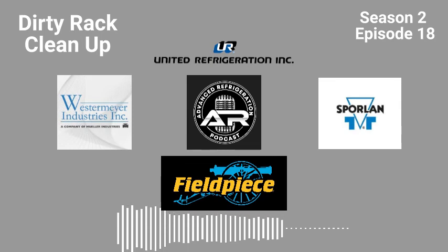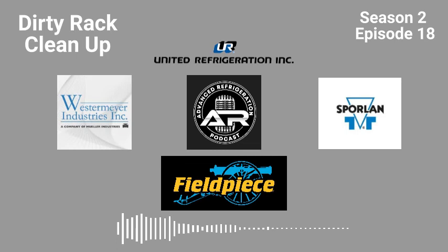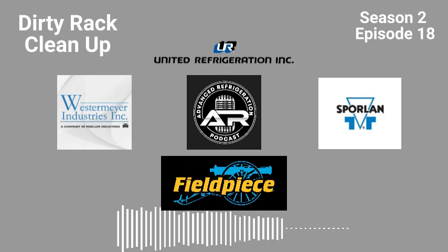Well, in the top of the York chillers, there's a little 90 there, and that little 90 gets a lot of heat from the condenser. So the little rubber grommet didn't really exist anymore. And I got like a tablespoon of water, maybe a teaspoon, on a 5-amp contactor at 460. It just shorted the shit out of it.